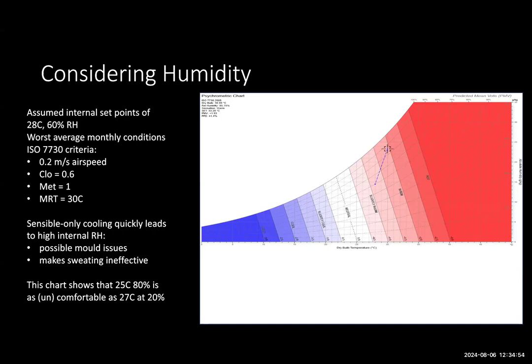air. But if we take that same meter cubed of air and reduce its humidity from 88% at 30 degrees to 60% at 28 degrees, that means we need to remove 9.2 grams of moisture. But the latent heat of water is 627 watt hours per kilogram. So that means we need 5.8 watt hours to make that same change in humidity. So for that air conditioning process of reducing the temperature and humidity, 90% of the energy required is going to be latent as opposed to sensible.